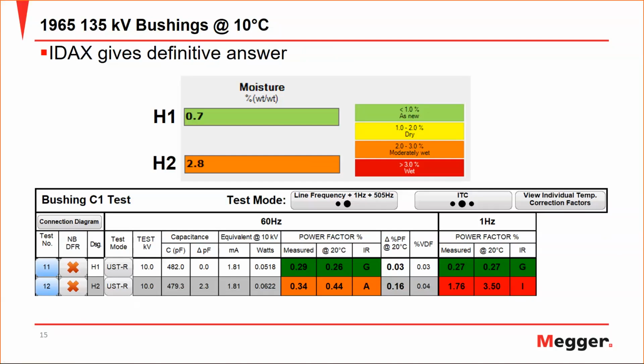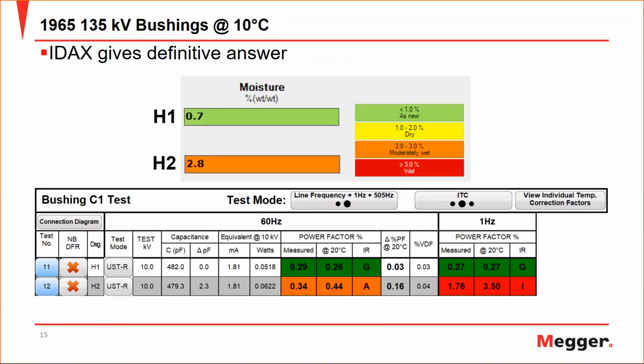Assessment of moisture per se is one of the properties of DFR, but with 1 hertz, we do see the sensitivity of the deviation of this dielectric response. So looking at this number, even if it's a trigger, it's a warning point. If it exceeds 1%, for example, on high voltage bushings, it's telling you it's about time to do further investigation. Don't just rely on the condition of the bushing to continue the operation, or schedule something in addition to that. That will be the full DFR test, of course. But again, don't think about moisture just as a typical issue on bushings. It could be mainly degradation or contamination of the insulation in the bushing. Okay.